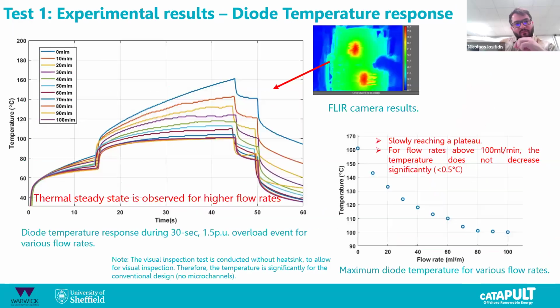Next slide. So here is a temperature response during this 1.5 per unit current overload. You can see that on a base plate only, that 0 milliliter per minute is a base plate only, like would be in a conventional structure. The temperature is 160 degrees C. However, it reduces all the way to 100 degrees C by using water flow at 100 milliliter per minute. Next.